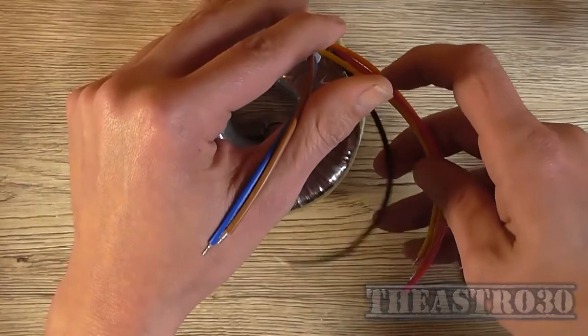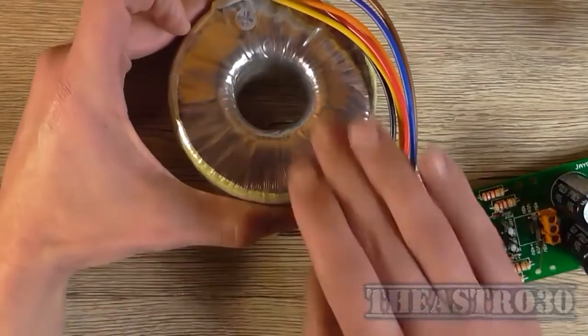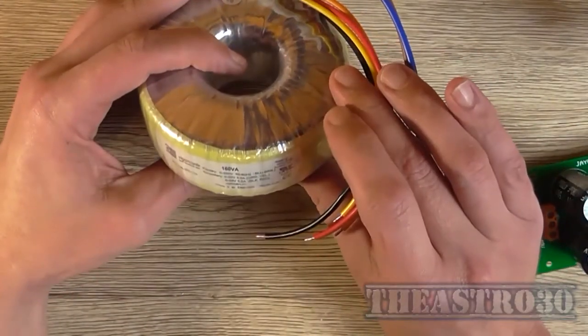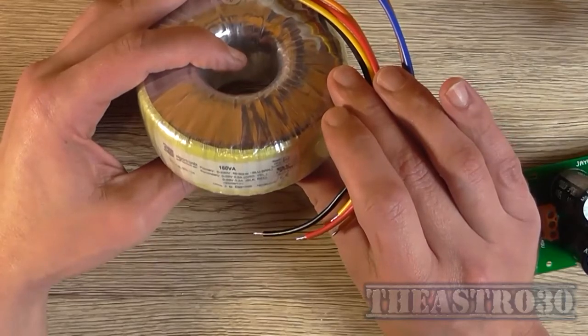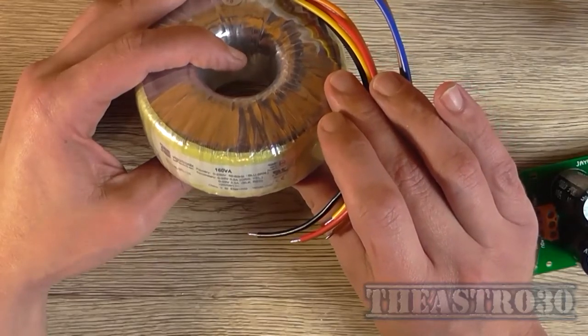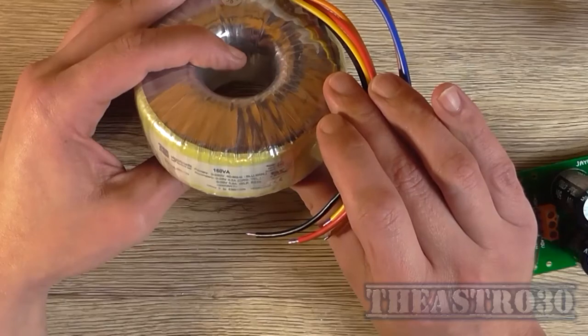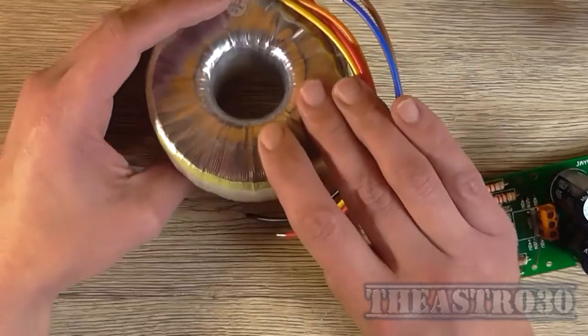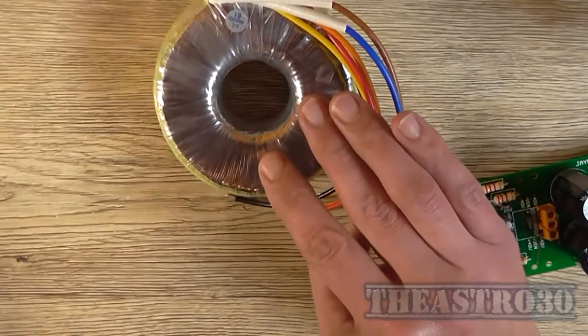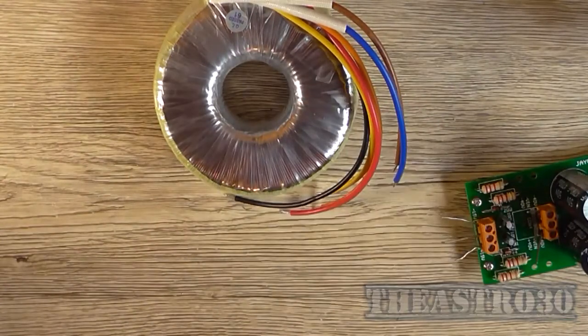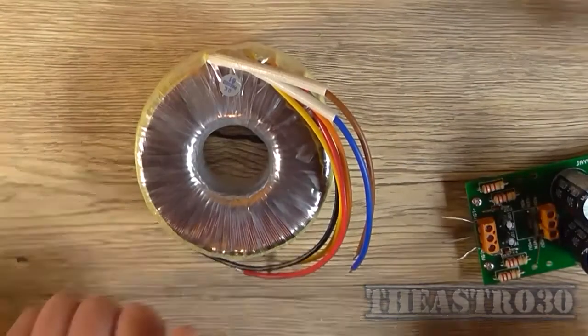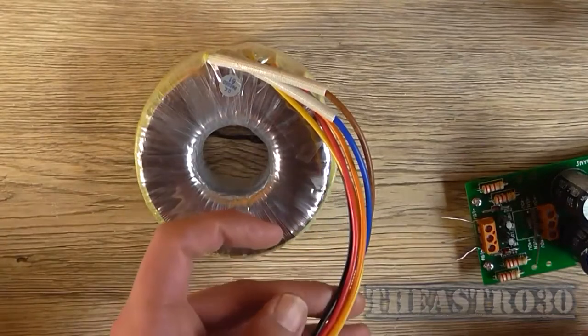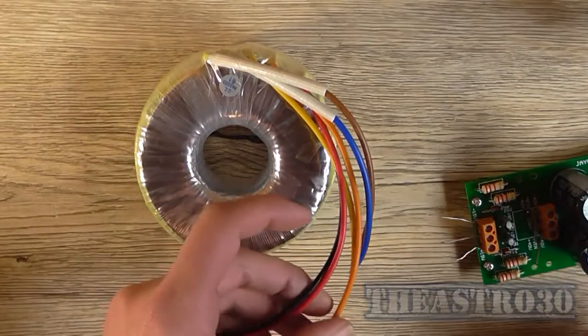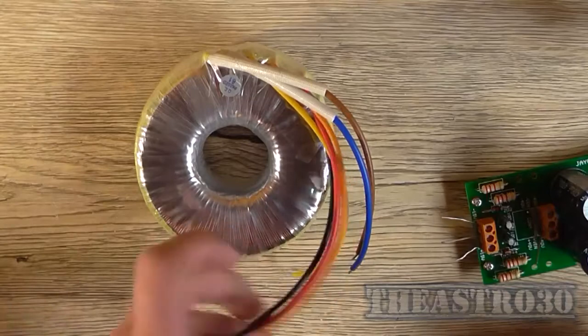These will be connected the correct way around. So we're looking at the orange, yellow, black, red for each winding, but I can't remember which order it goes in because it's not marked, and I don't think I marked it down. So I'm going to have to look up this particular model transformer, to see which part of the winding is which, like where the actual zero point is, etc.